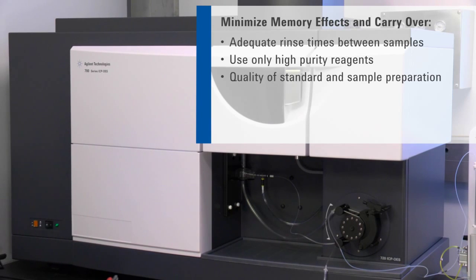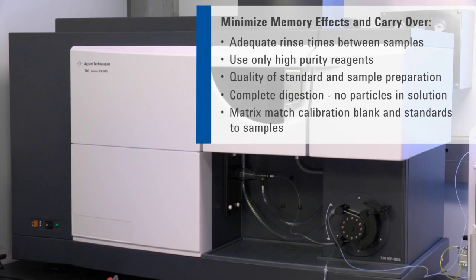Preparation of blanks, standards, and samples affects accuracy in a variety of ways. Verify that digestion is complete with no particles in solution. Finally, for optimal accuracy, always try to matrix match your calibration standards to your samples.